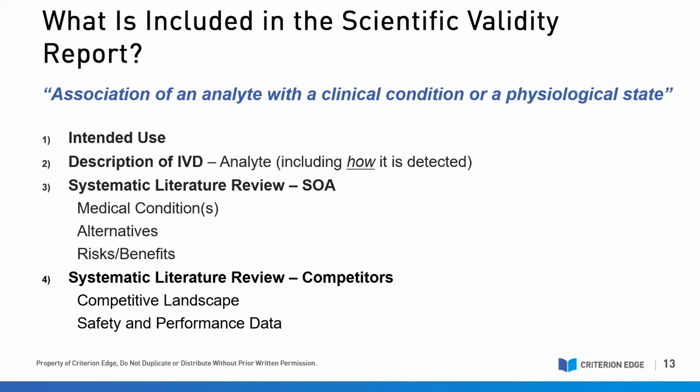But generally speaking, the approach to establishing the SOA is essentially the same as in the MDR world. IVD Article 56 describes the state of the art in medicine in relation to the performance evaluation concept for demonstrating scientific validity, analytical performance, and clinical performance. So the data and the conclusions constitute the clinical evidence by which you will demonstrate scientifically that you can achieve the intended clinical benefit. So in this case, we will conduct the first systematic literature review to support the SOA section because it is such a critical section.